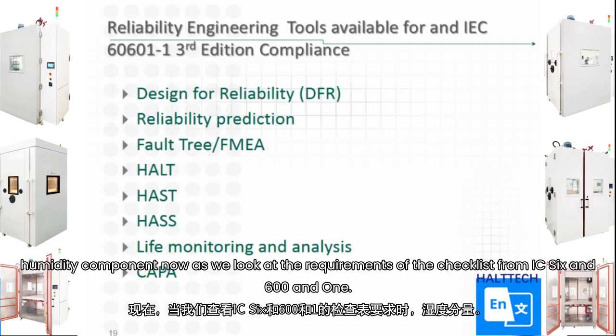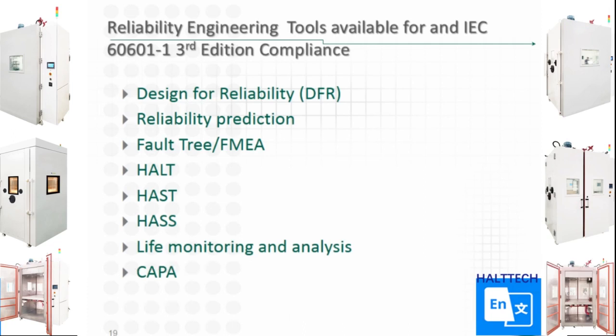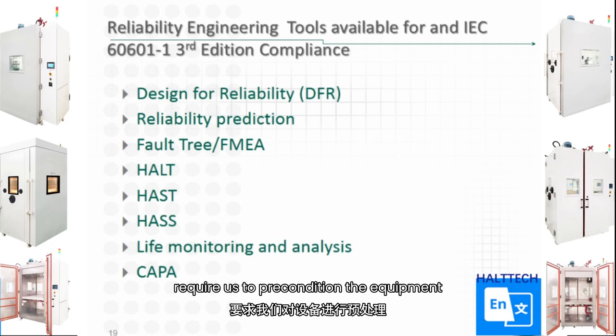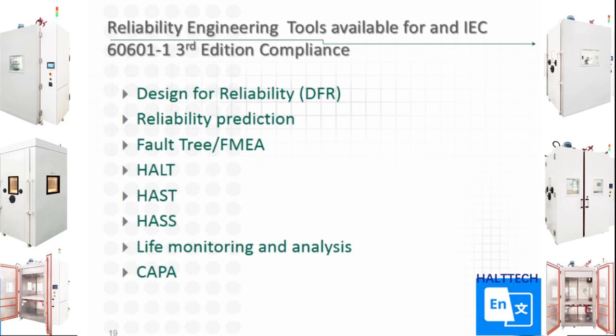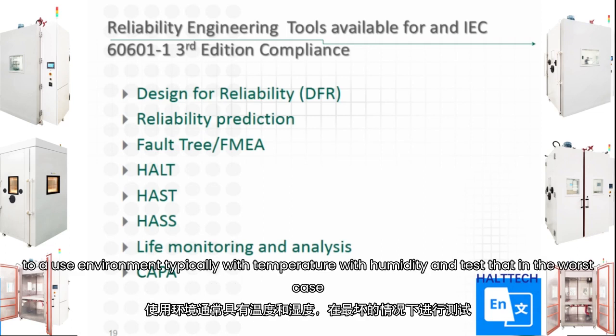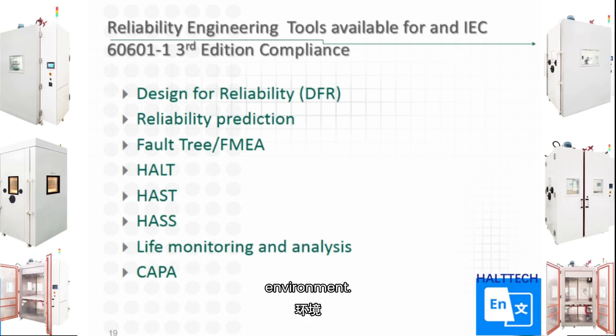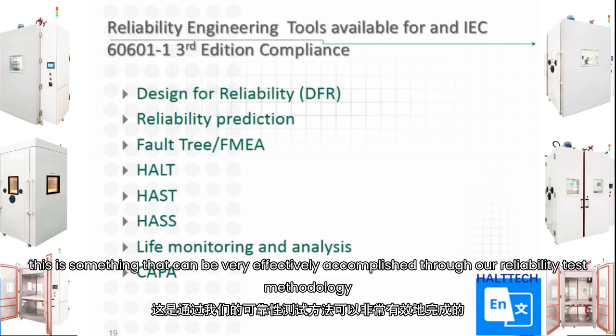Now, as we look at the requirements and the checklist from IEC 60601, many of those test requirements require us to precondition the equipment to a use environment, typically with temperature and humidity, and test that in the worst case environment. Once again, this is something that can be very effectively accomplished through our reliability test methodology.